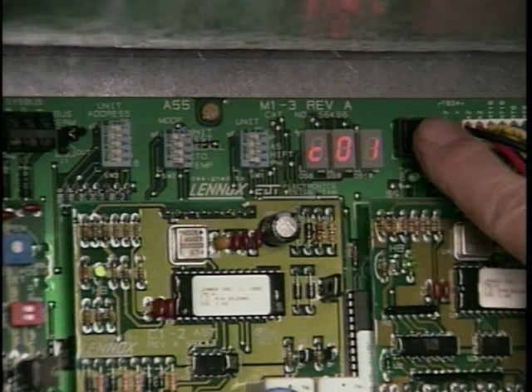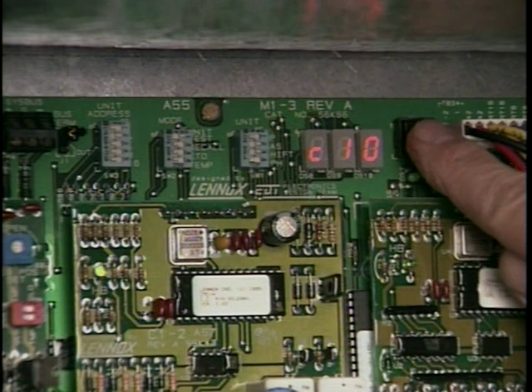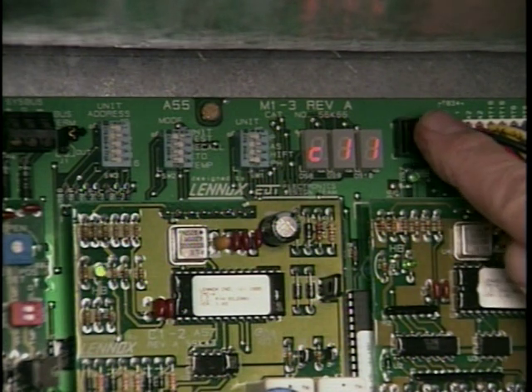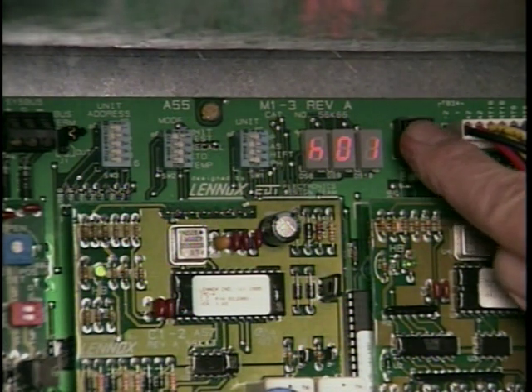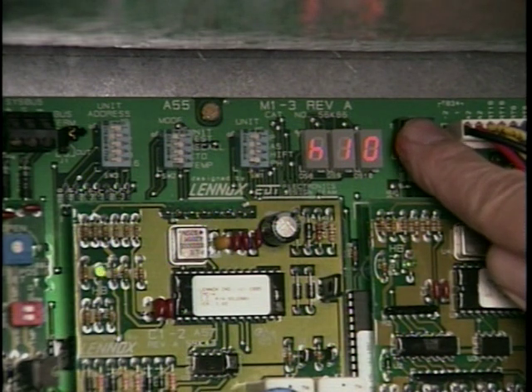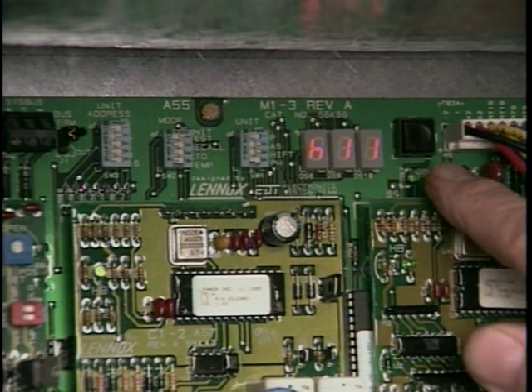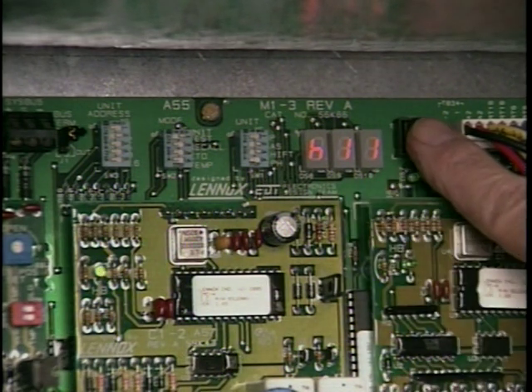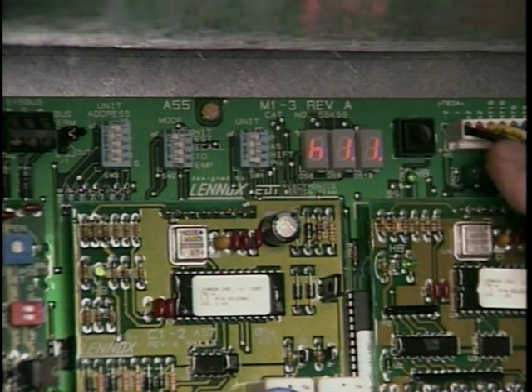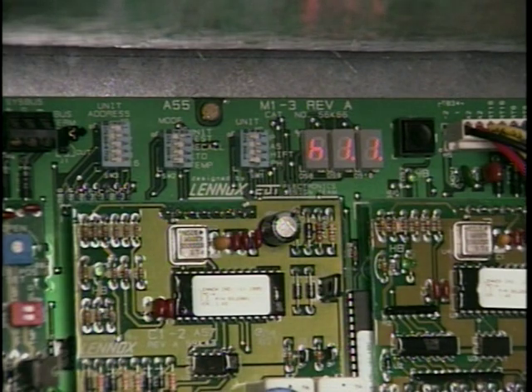The display should indicate C01. Now press the display push button 5 1-second presses to advance to H11 on the LED readout. Remember that to reverse the readout, you press the display push button 2 half-second presses. Now press and hold the display push button until periods appear in the display. The indoor blower and all stages of heat should start.